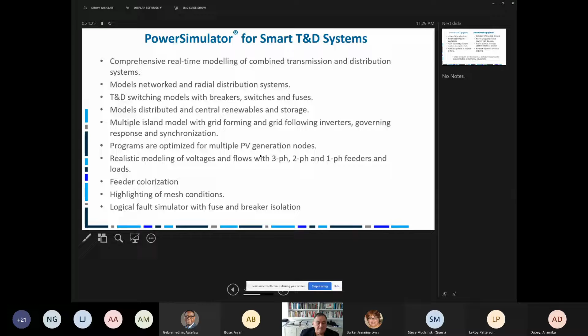Now, in transmission, when you have a fault on any element, there's a zone of protection that you have to clear and open the breakers to isolate that faulted device. In a distribution system, we're used to everything running radially. So in a distribution system, you're always looking at the next device upstream on the feeder. So simulating faults is very different between the two systems. But everything else can be done on a more common basis.